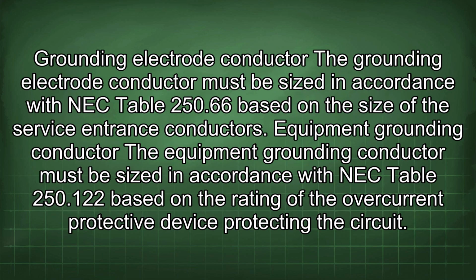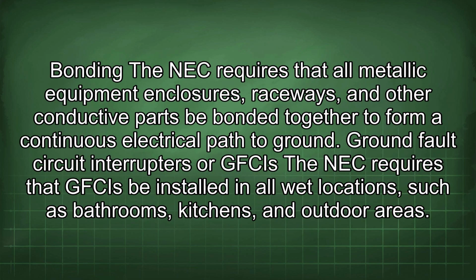Grounding electrode conductor. The grounding electrode conductor must be sized in accordance with NEC Table 250.66 based on the size of the service entrance conductors. Equipment grounding conductor. The equipment grounding conductor must be sized in accordance with NEC Table 250.122 based on the rating of the overcurrent protective device protecting the circuit. Bonding. The NEC requires that all metallic equipment enclosures, raceways, and other conductive parts be bonded together to form a continuous electrical path to ground.